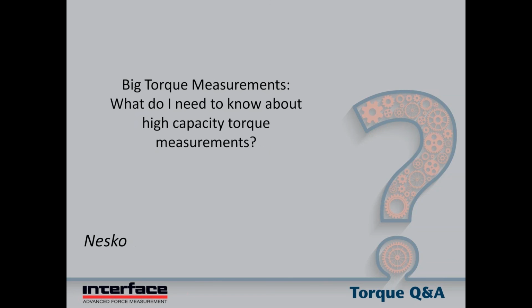Big torque measurements. What do I need to know about high capacity torque measurements? Well, one thing that comes up in many cases is that the higher capacity torque measurements are low-ish RPM, maybe not rotating particularly fast or through many rotations. And in that case, a reaction torque sensor starts to become attractive because large rotating sensors with bearings and things start to become quite expensive, and also they're just not as necessary. Again, if it does rotate through multiple rotations, though, a rotating sensor is required. Typically, Interface provides sensors up to about 100,000 inch-pounds in the rotary type, and that would be a flange style sensor or shaft style, and then above that they become shaft style sensors.